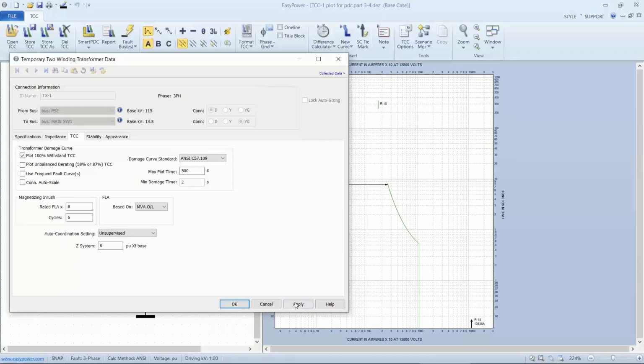This is the maximum that any fault needs to be able to protect against. So that gives us this dotted straight line. This is the worst case, 100%. You want to not exceed this curve, either at the time-current plot up and to the right, at any point in the life of the transformer.